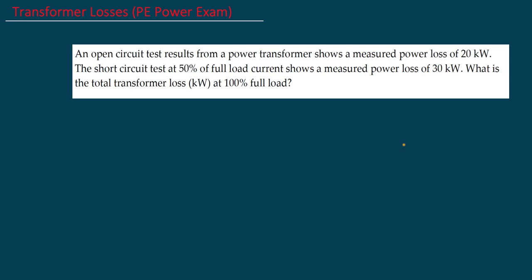The question is: what is the total transformer loss at 100% full load? First, you need to understand what an open circuit test versus a short circuit test is. The open circuit test determines the transformer losses at no load. The short circuit test determines the winding resistance, leakage, and leakage reactance.